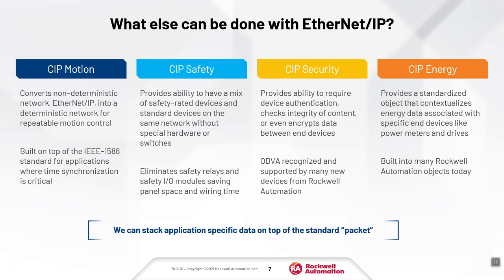In addition to CIP Motion, we have CIP Safety. CIP Safety allows us to control a mix of safety-rated devices and standard devices on the same standard Ethernet network without any special hardware or switches. This means you have the ability to eliminate expensive devices in your control panels like safety relays or safety I/O modules, which can reduce panel space and also save on wiring time.